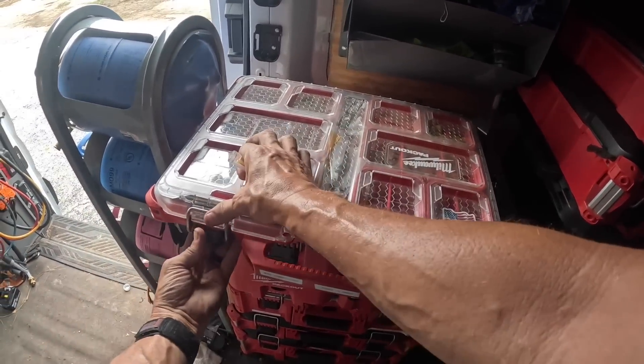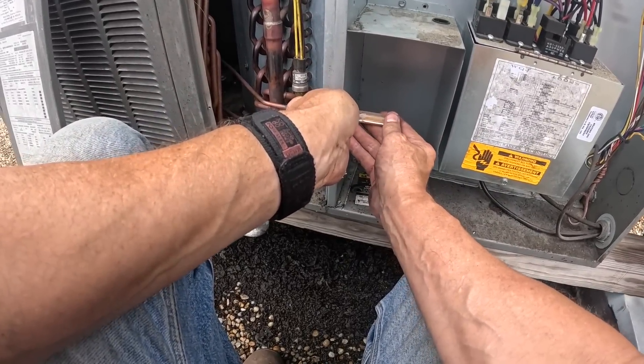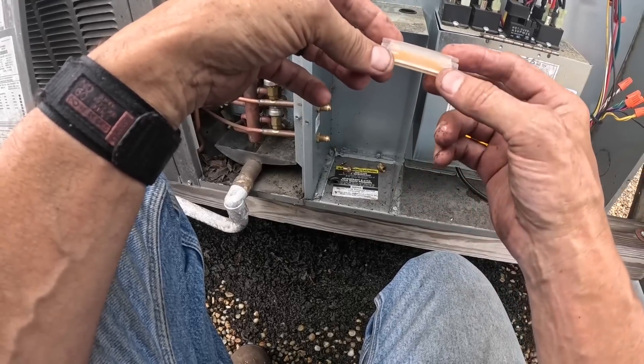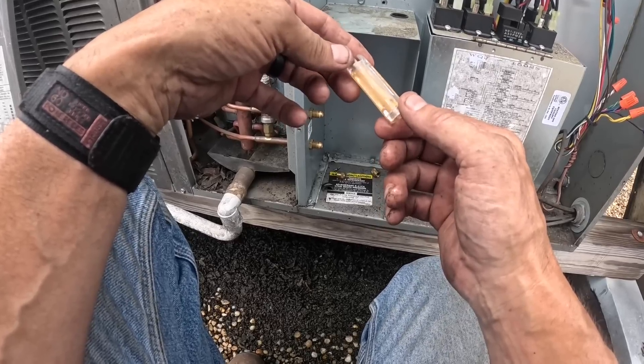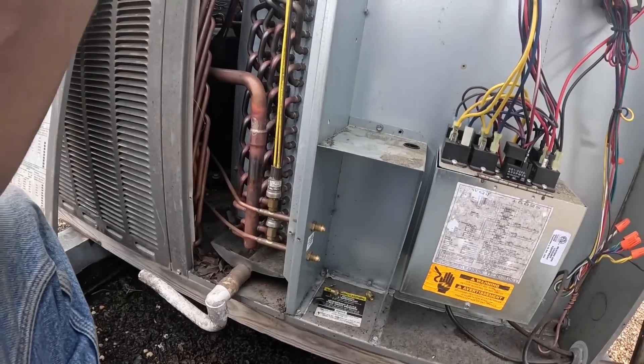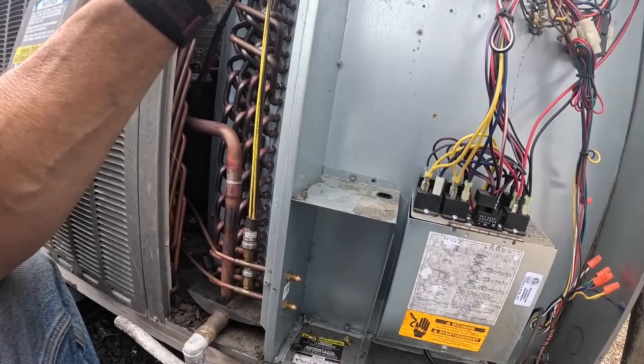It's an old one but it'll do. If this turns red or pink, that means we've got acid in the system. I don't see it turning red or pink — watch that for just a second. That's frustrating.